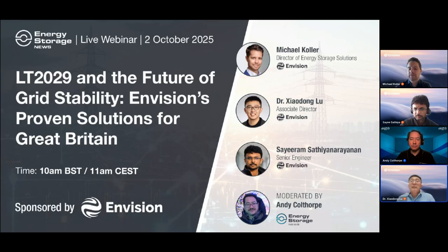And with the technology itself, we really provide an instantaneous response to the rate of change of frequency or short circuit level, because you are a voltage source. When there's a voltage difference on the grid, when there's a phase shift on the grid, the voltage and phase difference between the two voltage sources generate the active power or reactive power directly. So we can't really see a delay from it. Yeah, that's it from my side. Thanks.